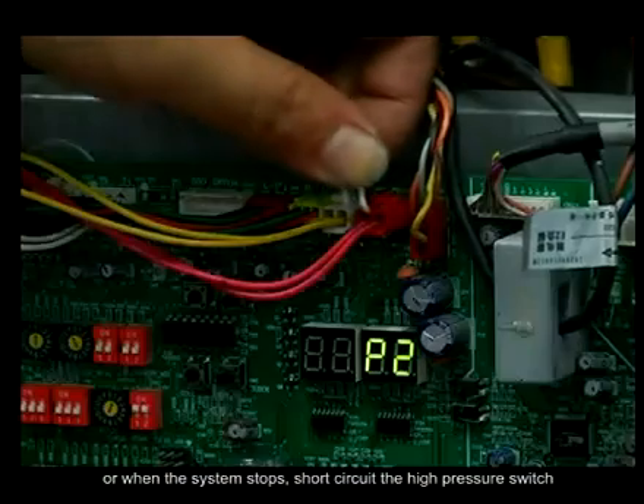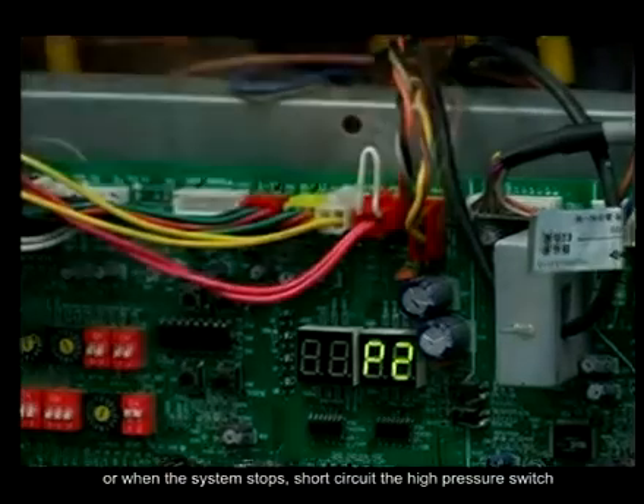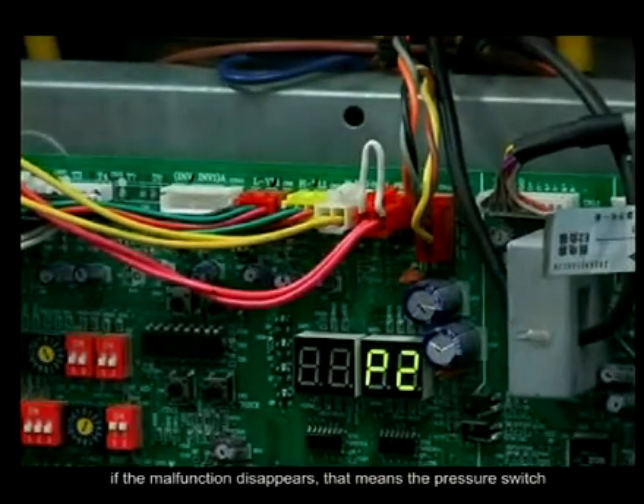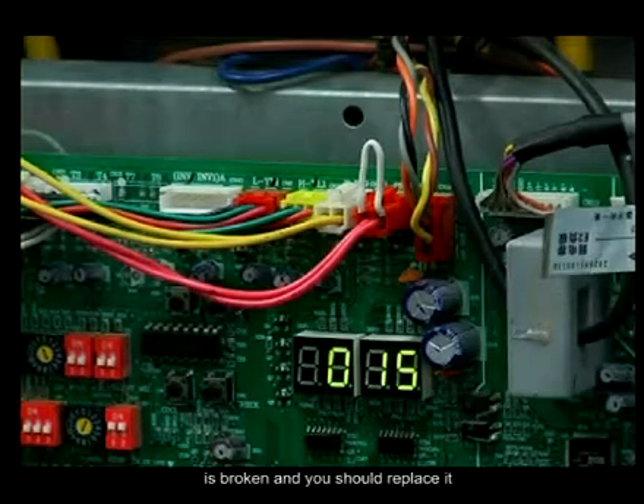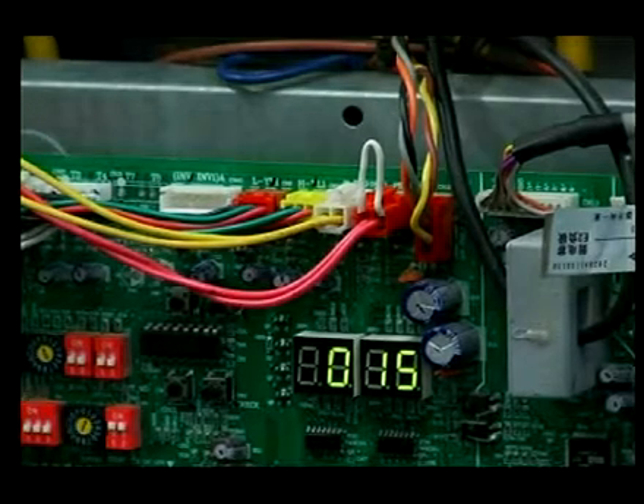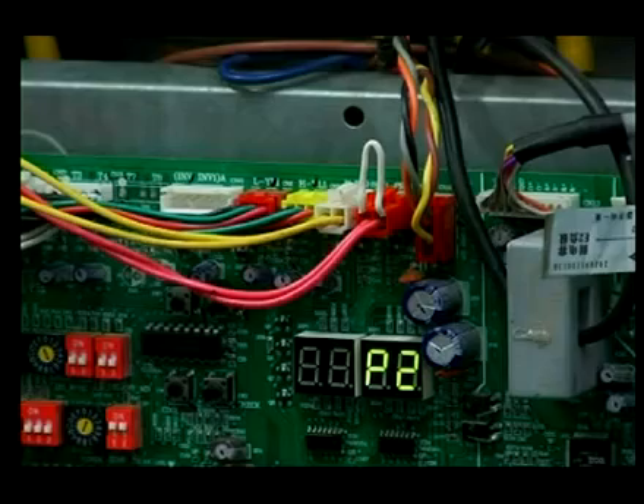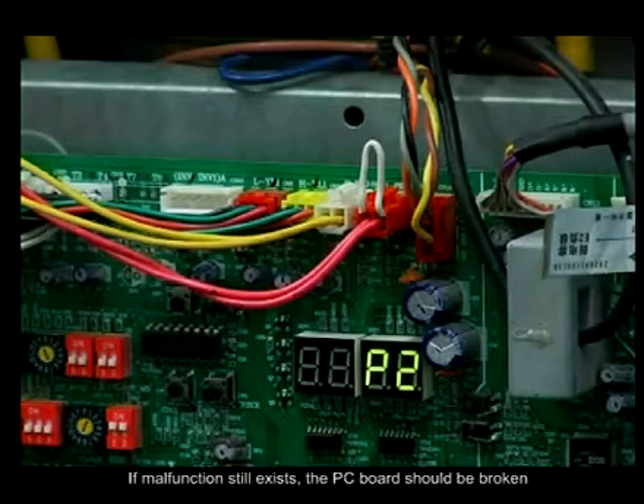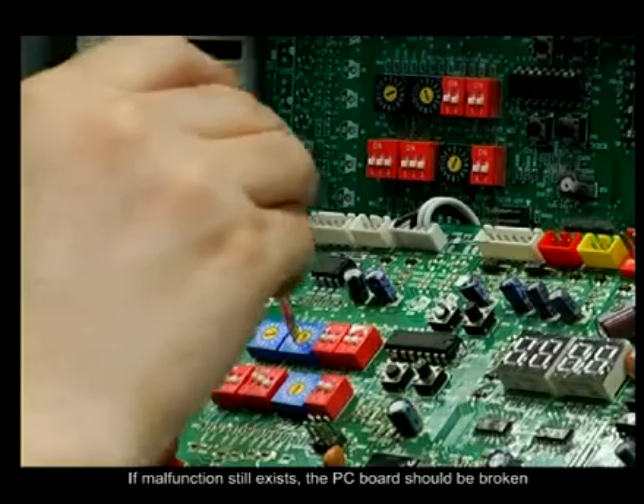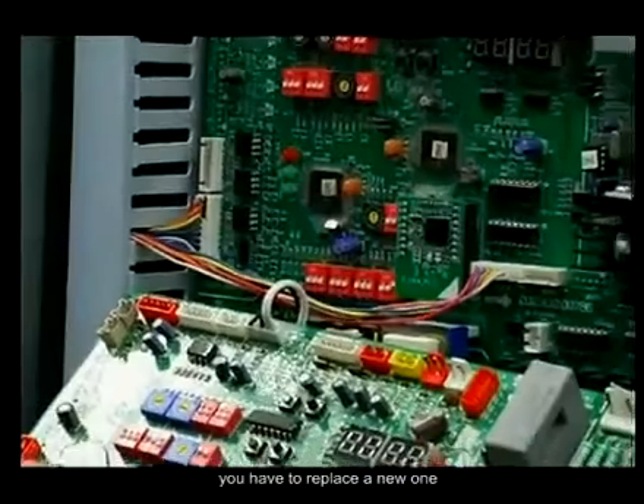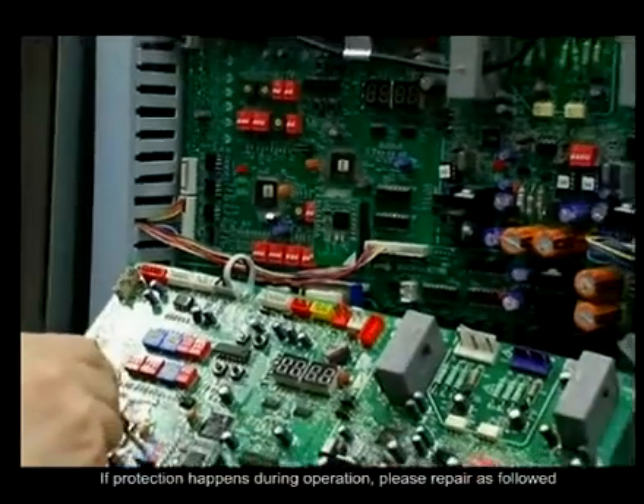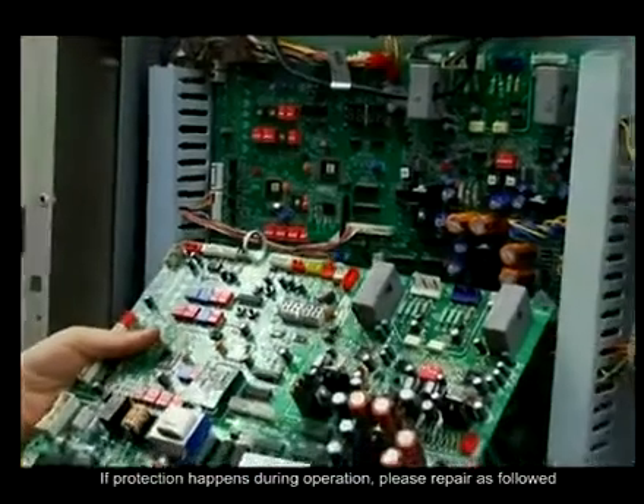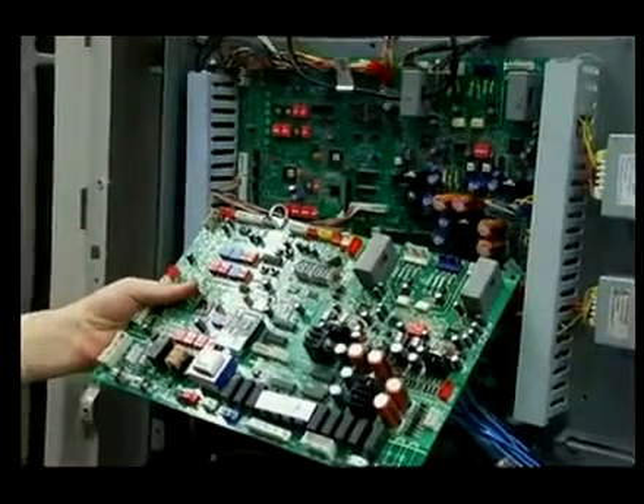Or, when the system stops, short-circuit the high pressure switch. If the malfunction disappears, that means the pressure switch is broken and you should replace it. If malfunction still exists, the PC board should be broken. You have to replace a new one. If protection happens during operation, please repair as followed.